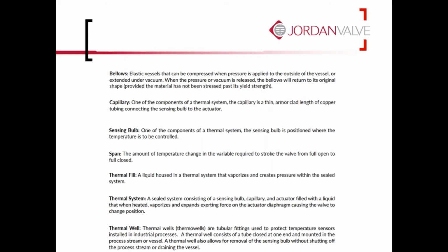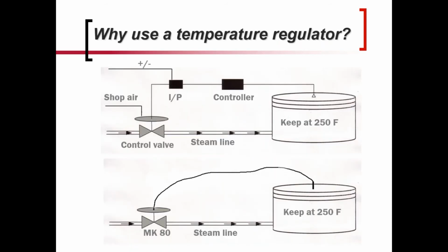And then thermal well is just a fitting that goes into the tank or the heat exchanger, and then the actual bulb, sensing bulb, is placed in that so that if you need to change that or you need to do maintenance on the bulb, you don't have to drain whatever it is you're controlling the temperature of. So those are all very relative to these types of applications.